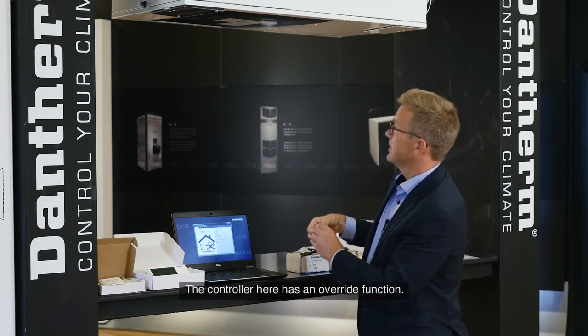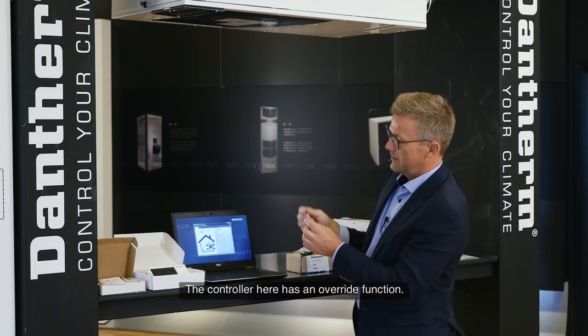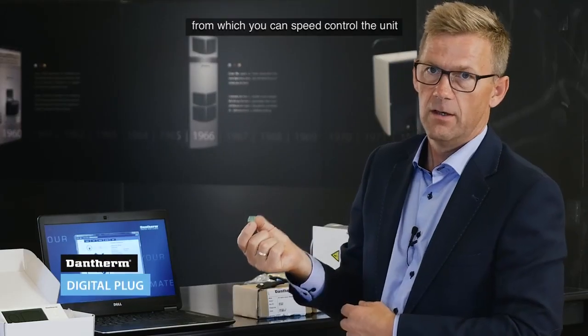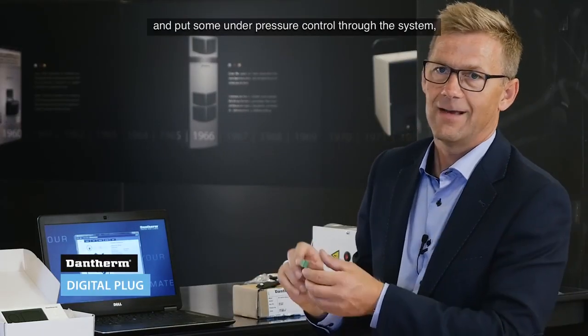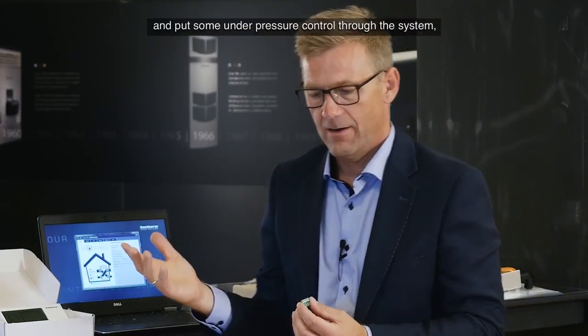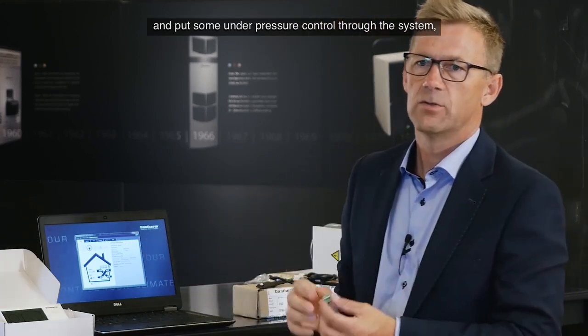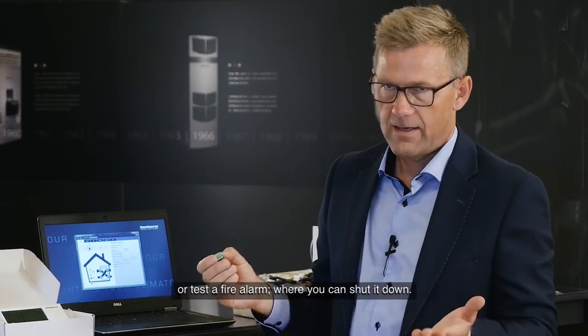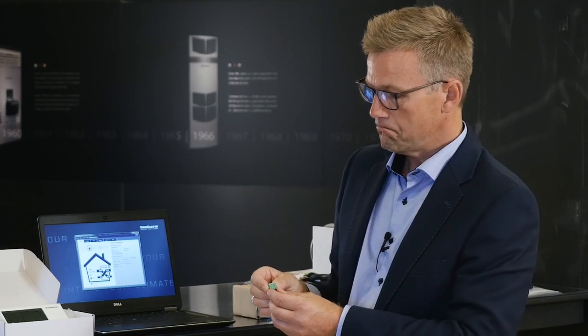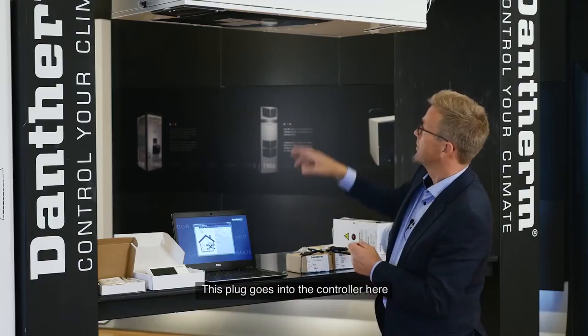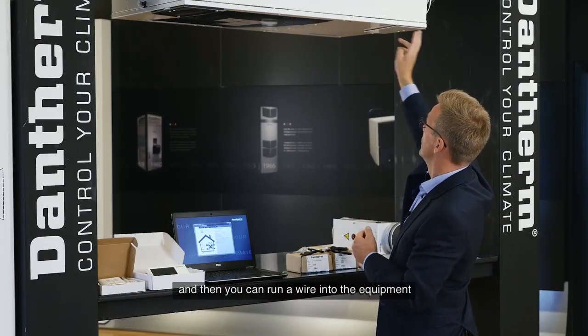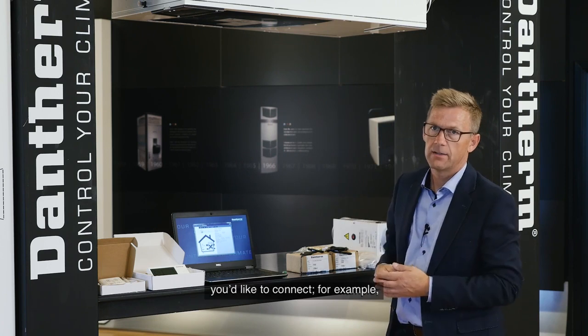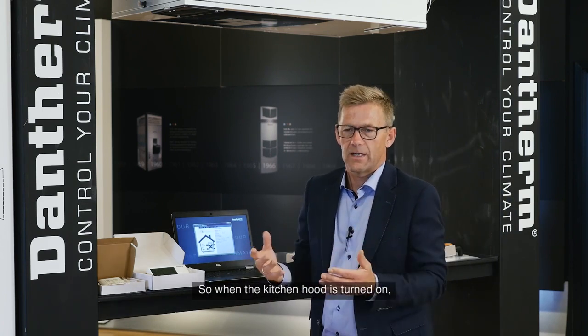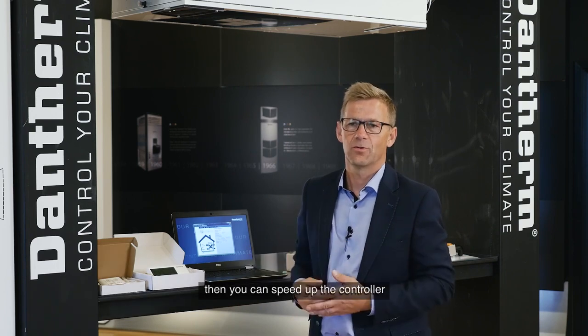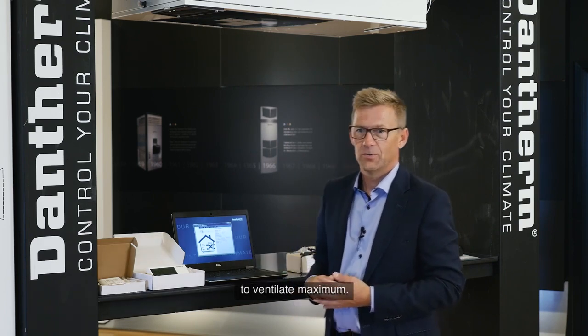Then the controller here has an override functionality, because there are 2 digital inputs from where you can speed control the unit, and you can also connect an under pressure control system or a fire alarm, or you can shut it down. That plug here you plug into the controller, and then you put the wires into the equipment you would like to connect, for example a kitchen hood control, so that when your wife is starting the kitchen hood, the unit will go to speed 4, for example, to ventilate maximum.